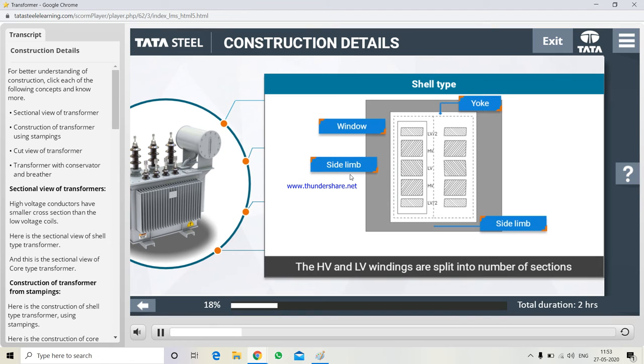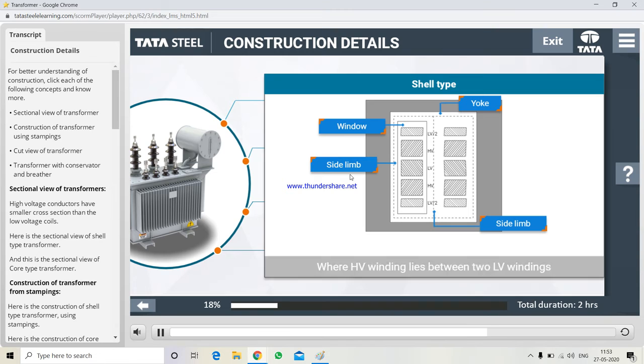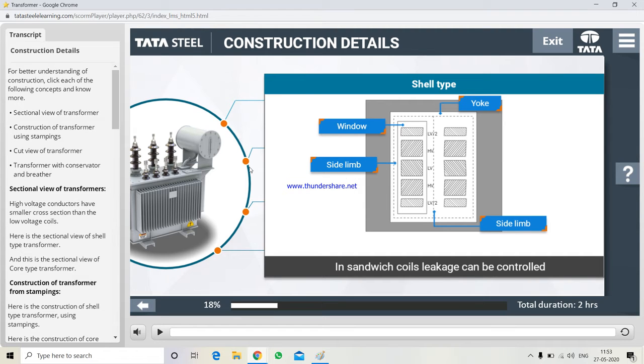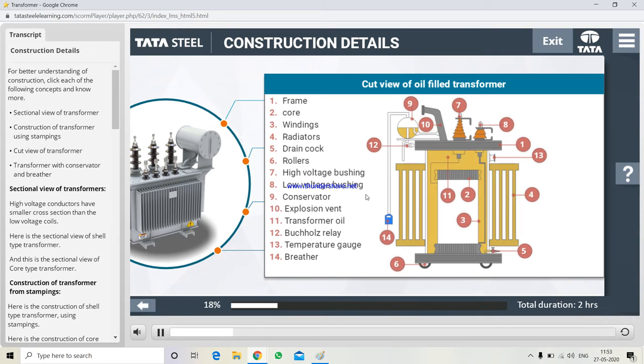The HV and LV windings are split into number of sections, where HV winding lies between two LV windings. In sandwich coils, leakage can be controlled. Let us look at the cut section of transformer to understand it more clearly.